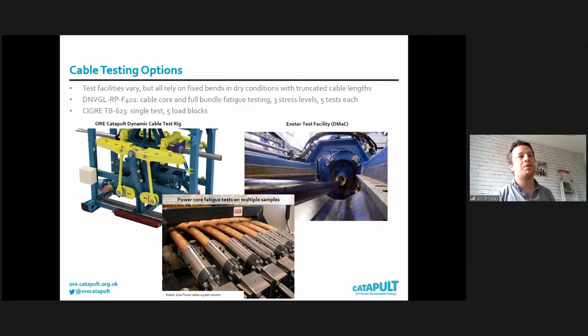That doesn't really tell you very much about how good the cable is in fatigue and how it performs relative to other designs. So if you look for other standards like the DNV F401 standard, they actually ask for 15 tests. So you can start to characterize the stochastic nature of fatigue and actually get a better understanding of how these components fatigue. And I think that's particularly important for the individual power cores because they're quite a complex construction. There's a lot that could go wrong, particularly with the copper. So getting a good fatigue curve on those is going to be very important going forward.